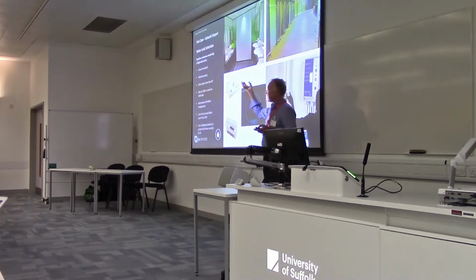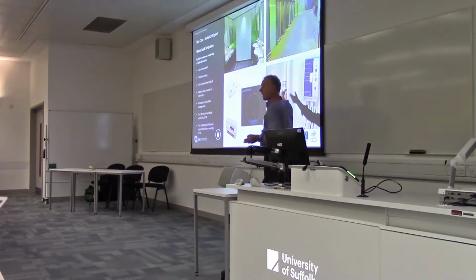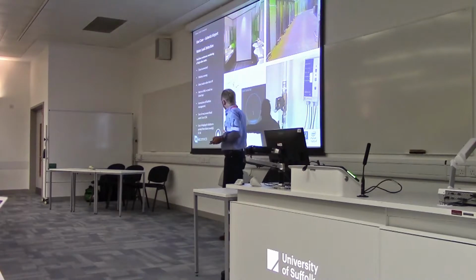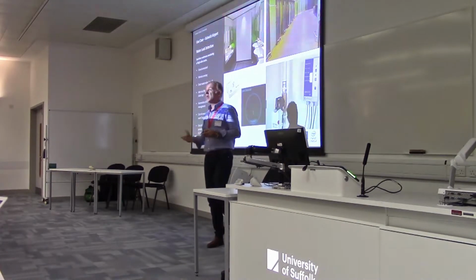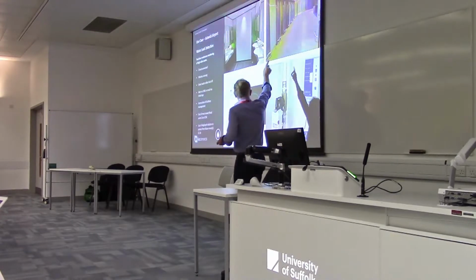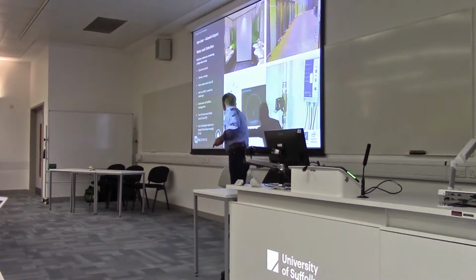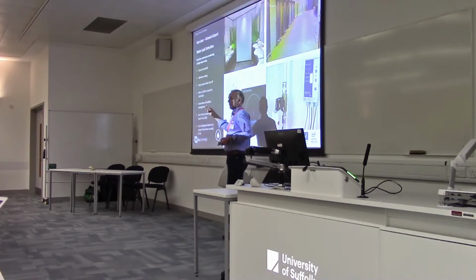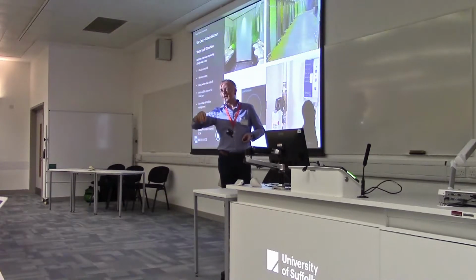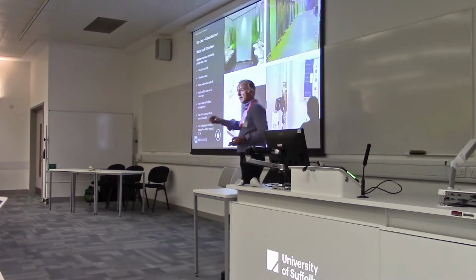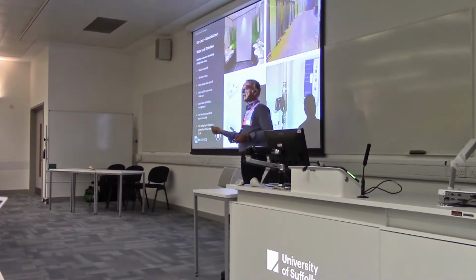Because the transmit and receive devices that were installed are within a 30 metre radius of this, all we had to install was these little bad boys. So these are £150, £100, something like that, as a leak detection device. Energy harvesting, no batteries. Sits there, minds its own business at the back of these, where the pipe work and what have you is. In the event of a leak, it does nothing more than expand these little bushes, triggers a signal, and an EnOcean relay now sits next to the isolation valve, so the minute there's a leak, it turns the water off. Sends a tweet, sends an email, and sends a message to the guys to say, we've just had to turn the water off, guys, there's a leak, no damage.